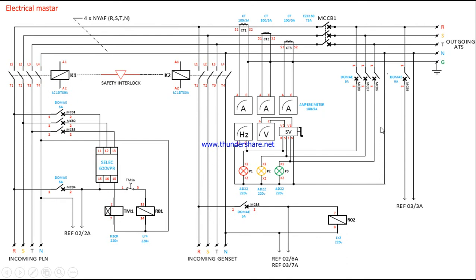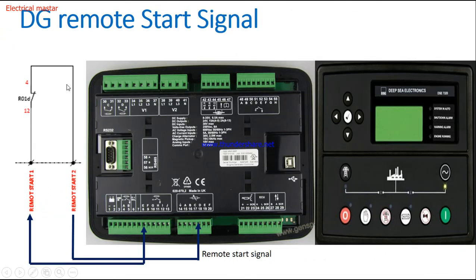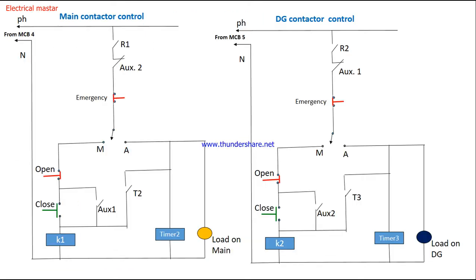In summary, whenever the main supply is received, the MCBs are closed, the phase failure relay senses the voltages and closes terminals 15 to 18, the timer activates, and after a 3–4 second delay the timer NO closes, activating R01. When the generator is already running and the main supply comes back, a delay time is given before the generator stops. After 2–3 seconds R01 picks up, its NO closes the main contactor, and the 12V remote start signal is removed from the DSE controller, so the generator switches off. This is how the ATS panel operates.